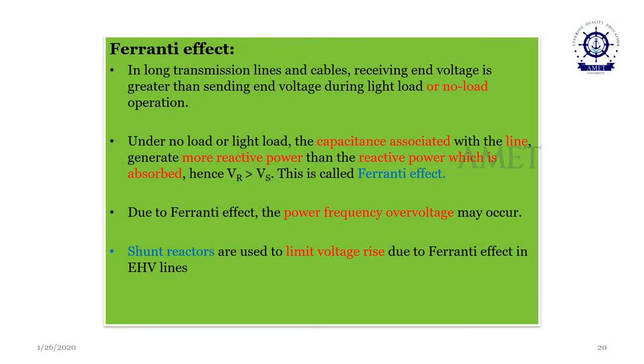The next very important and challenging cause of temporary overvoltages is the Ferranti effect. We know very well this Ferranti effect mainly occurs in long transmission lines, not in short or medium ones, where the impact is not great. But in the case of long transmission lines, it has to be taken care of. What does this actually mean? We know our transmission line is made up of R, L and C: resistance, inductance and capacitance. We should never operate the transmission system under lightly loaded or no load condition.